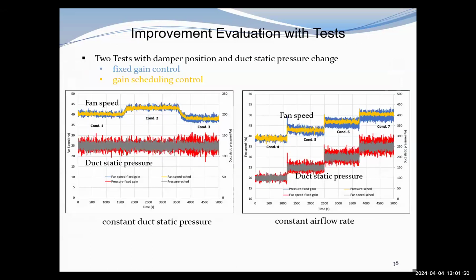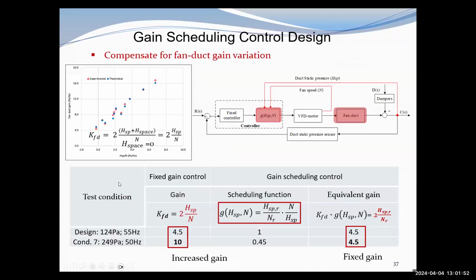If you see, this fan duct gain is proportional to the ratio of duct static pressure over the fan speed, and either change will change the fan duct gain. Higher duct static pressure will give a higher fan duct gain, or lower fan speed will result in a higher fan duct gain, and then a more aggressive response. Okay. Thanks.